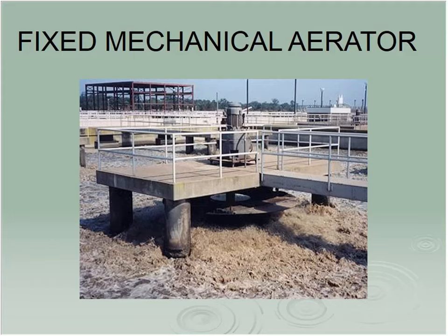But if I'm going to form a nice floc particle, then I've got to take it through my mechanical mixer, whatever we're calling it, and I just churn it up. The other thing is, if you think of it, these tanks are rectangular. So this is centered somewhat in the center of the tank. How well is my aeration in those corners, quite a distance from that mechanical mixer? And if I have low DOs there, then S-Natans and some of those other low DO elements could thrive and give me troubles.